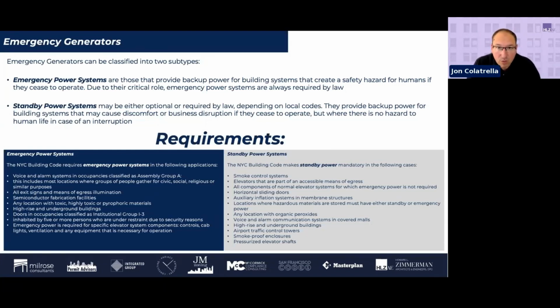The most important thing to take away is that if you have an older building that doesn't require a standby generator, but the owner or operator wants to elect to put one in—as soon as you go into that category, especially in New York City, there will be a minimum set of things that have to be connected, in addition to the nice-to-haves like convenience outlets, possibly domestic water pumps, and other things that make the building comfortable in a power outage. So even if electing to install a standby power system, you're going to have to connect emergency lighting, fire alarm, and an elevator to serve all floors at minimum.